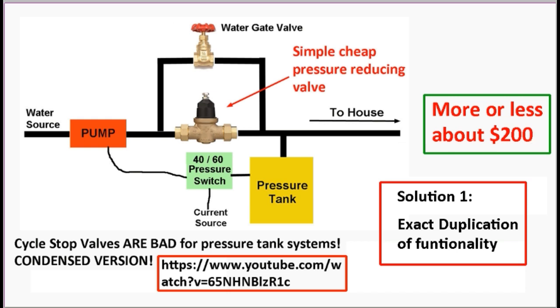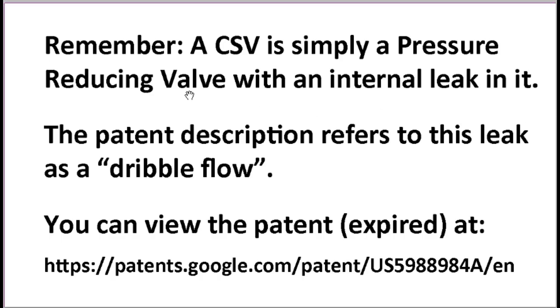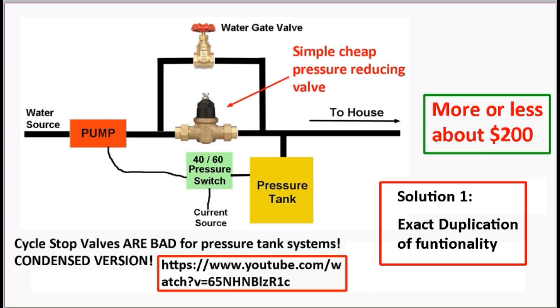And if you don't believe me, you can go to their patent page, which is right here. Remember, a CSV is simply a pressure reducing valve with an internal leak in it. The patent description refers to this leak as a dribble flow, and you can view the patent, which is expired, at this site. If you view this patent, you will see that a cycle stop valve is simply a pressure reducing valve with an internal leak. So let's go back to my picture now.